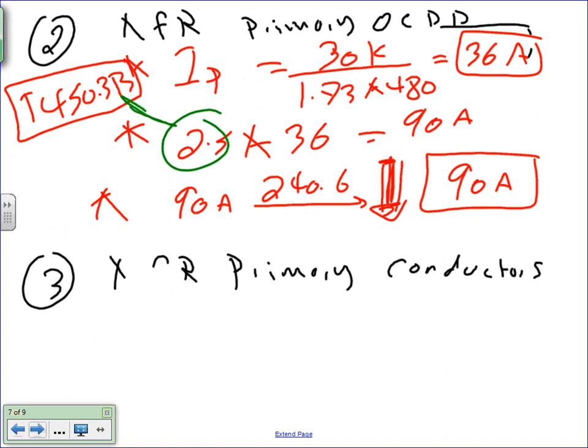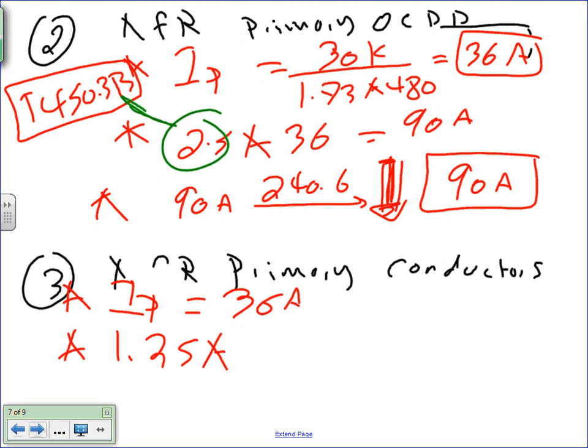Primary conductors, same thing for primary I. You take I primary equals, guys, 36 amps, right? Now, this is one. Number two, I want to assume continuous load, 1.25 times 36. I'm assuming I'm taking the full load amps out of this transformer continuously. That's my assumption. Reasonable assumption, though. I used to size based on 36, but it's a good idea to size based on 45. You allow them to use the full capacity of that transformer. Okay, I think 45, Chris, 45 amps.